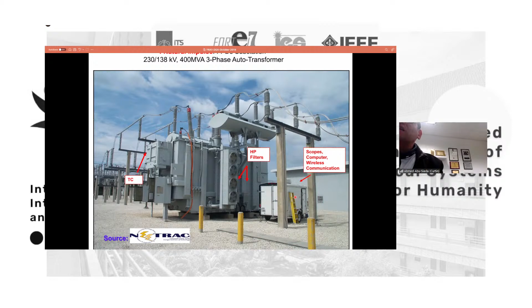People in industry in Florida started thinking about that. They looked at this auto transformer with a tap changer and high pass filters, and connected their measurement devices and scopes here. They didn't connect anything artificial; they just connected their scopes and tried to use the natural lightning impulse as a source for the FRA, without connecting it to an external source. And they were successful.